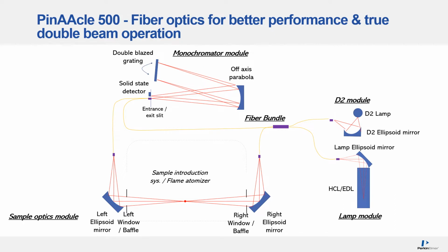Background correction is performed using a high-intensity deuterium arc lamp as the continuum source. This provides fast startup, exceptional long-term stability, and optimum analytical performance for flame.